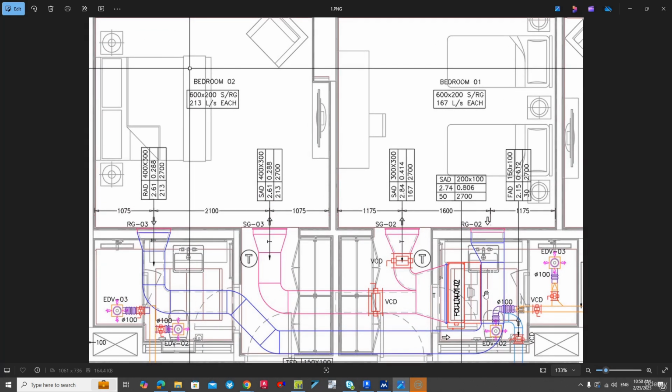For example, in hotel rooms and residential apartments, we put the AC equipment in the toilet ceiling if we don't have spaces to place it somewhere else, as the false ceiling in toilets is lower than other areas. So we cannot use the free return system because of the toilet unpleasant air. So we use the return ducted system as you can see in this apartment.